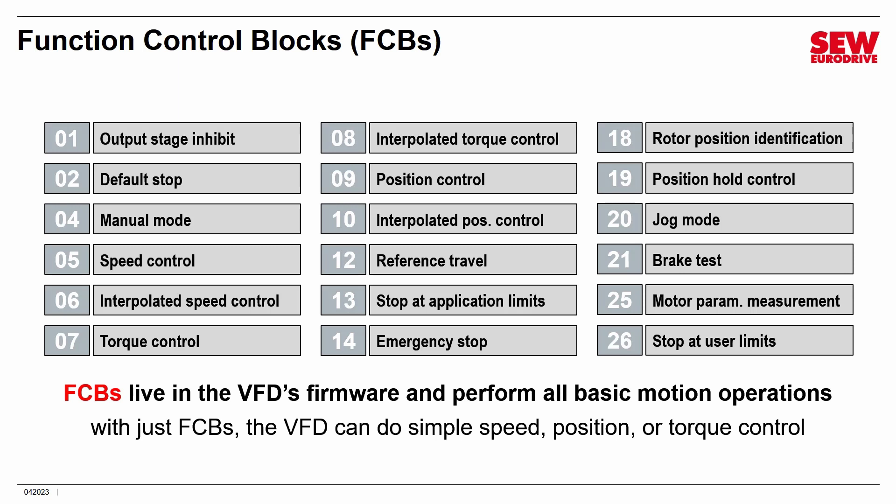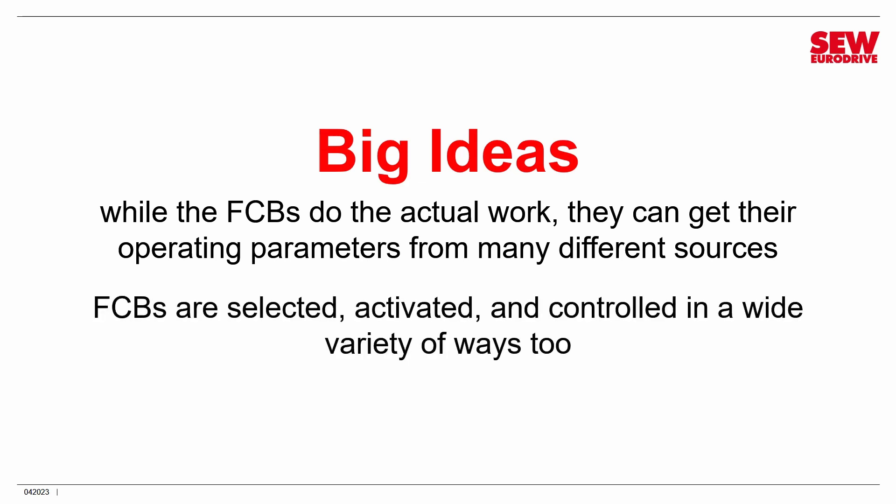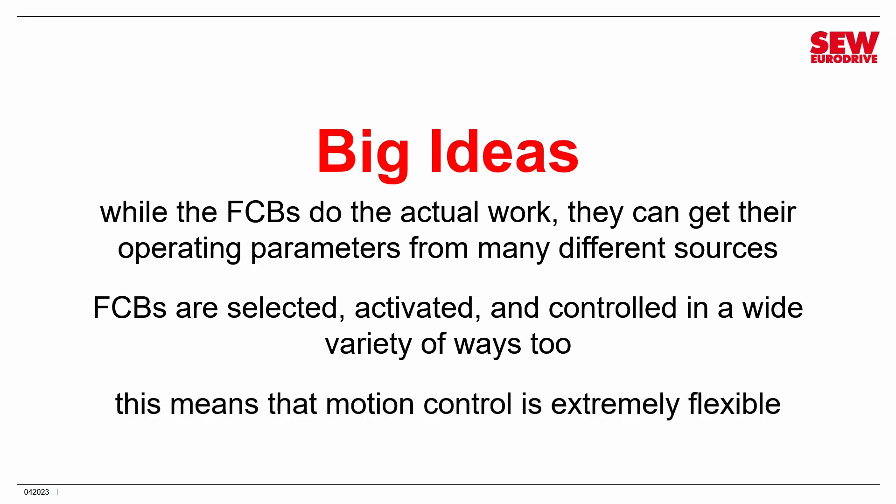Each FCB is almost just like a little routine that can do one specific kind of motion. With just the FCBs, the VFD can do simple speed, position, or torque control, which in many applications is all you need. Simple shaft-spinning applications greatly outweigh the exciting ones like robotics and camming. FCBs alone can do an awful lot, and that's what we're going to be playing with in the next few labs. Now, a few big ideas: while the FCBs do the actual work, they get their operating parameters from many different sources — that is why the Movi-C product is such a powerful and flexible product.